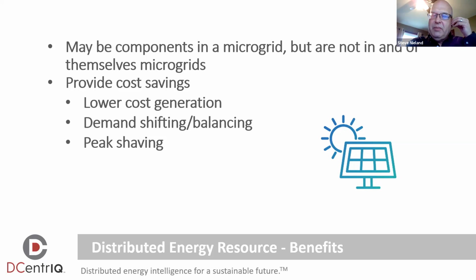We can also use storage for peak shaving. The utility looks at my highest demand within a year, in kilowatts during my demand period—in the state of Wisconsin, for instance—and whatever peak I hit becomes the demand rate I'm charged for the rest of the year, whether I reach that peak again or not, since they want to ensure capacity is available if needed. By using energy storage, I can cut back on how high that peak goes by discharging a battery when I see a rapid increase or approach a certain usage threshold, clipping off that peak and lowering demand charges.